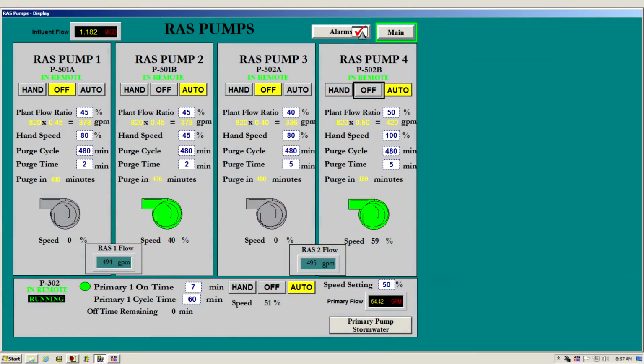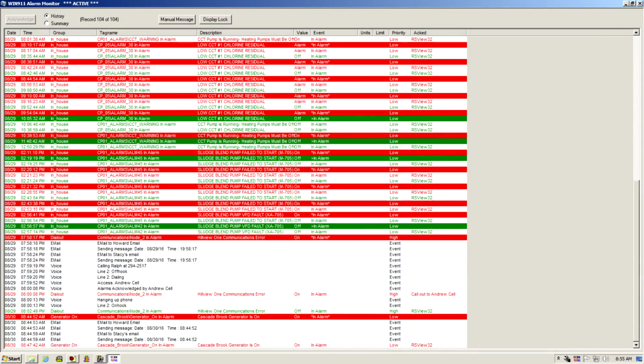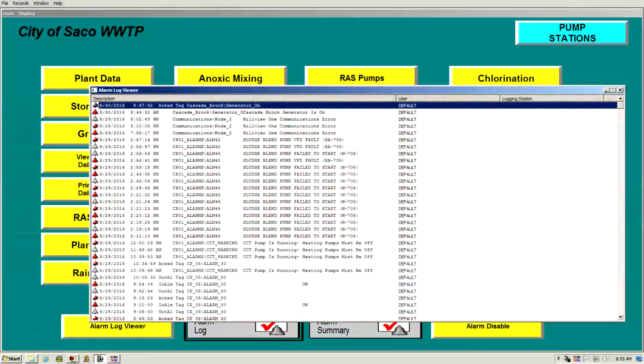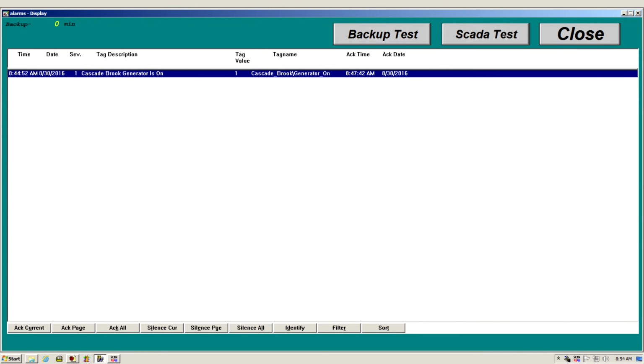The system also allows for alarms to be relayed to our Win911 software, which phones and emails alarms to the staff. 2 members of the staff are on call during non-business hours at all times. They are able to view alarms and log into the SCADA system via their cell phone, computer, or tablet. If by chance there is a malfunction of the Win911 software and an alarm is not acknowledged, a backup dialer is activated and will phone the deputy director until the alarm is acknowledged.